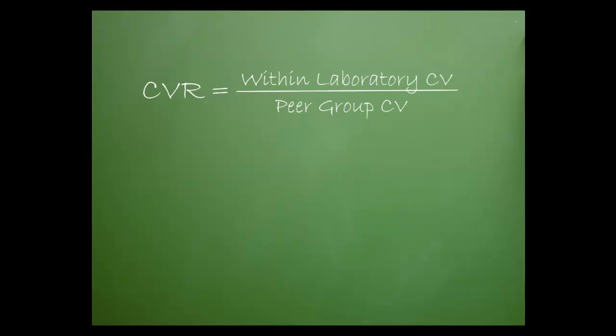Let's look at an example. If the CV for potassium on a particular instrument is 4%, and the potassium for all other laboratories using this same instrument is 4.2%, the CVR is 4 divided by 4.2 or 0.95.